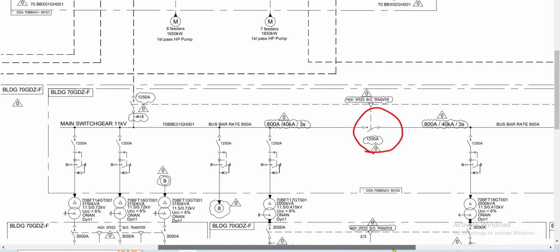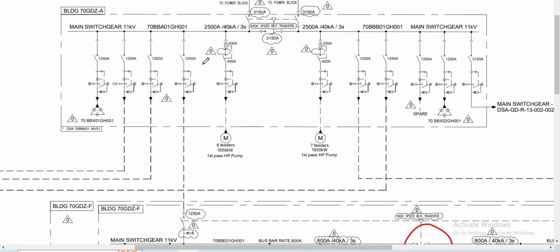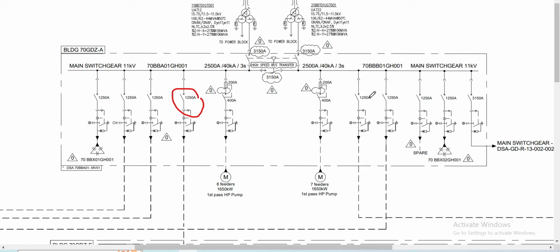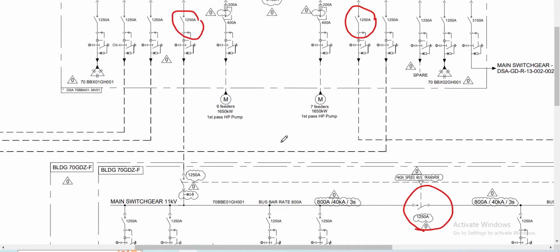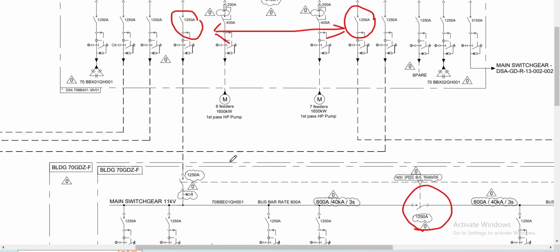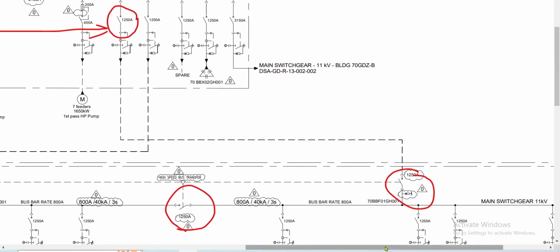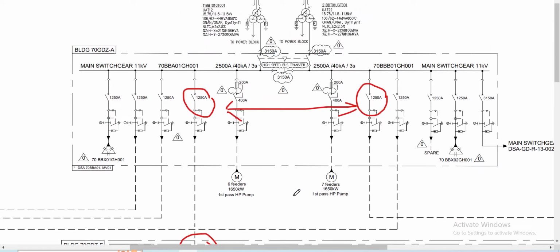The second video that we prepared is regarding the protection relay setting of the relays which have been installed at this point here, the outgoing feeders from building A 11 kV switchgear, and also this point here. This is the feeder which supplies power to our 11 kV switchgear at building F. So on our second video, the settings on these relays are also the same settings for our incomers of this 11 kV switchgear from this building F. So that was our second video.